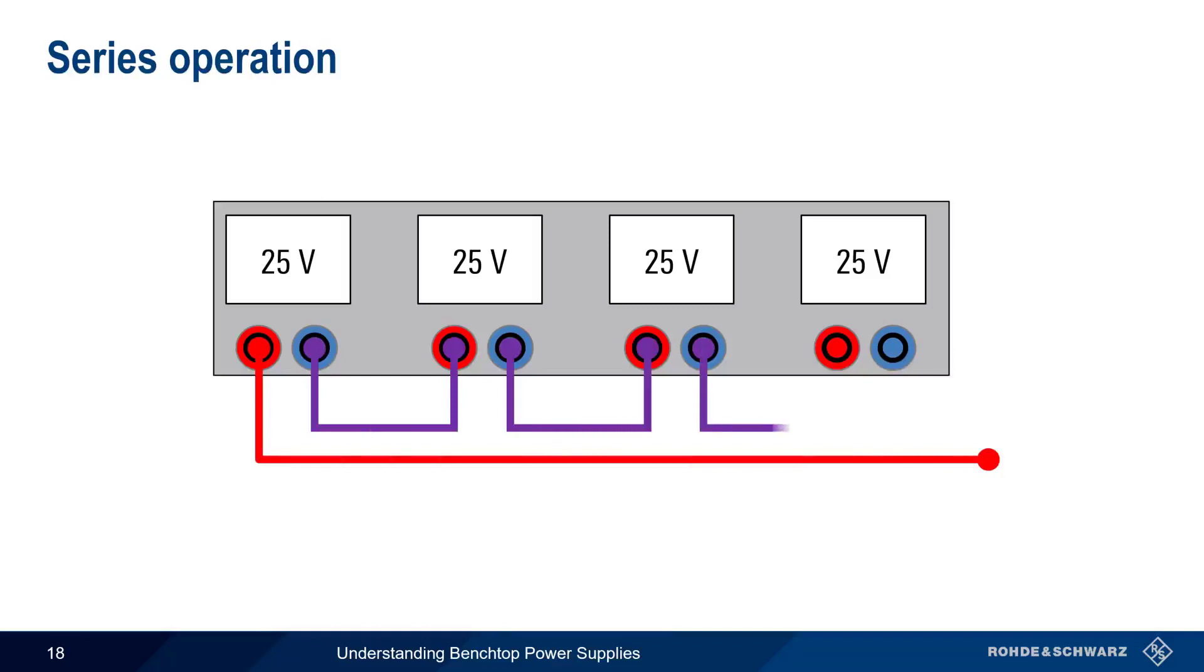Let's look at an example of series operation, which combines channels in order to produce higher voltages. We'll start by configuring each of our four channels to output 25 volts, and then connect them in series. The result is a combined output voltage of 100 volts. Note that the channels don't all have to be the same voltage. We could also use this combination of different voltage settings to obtain the same 100 volts combined output.